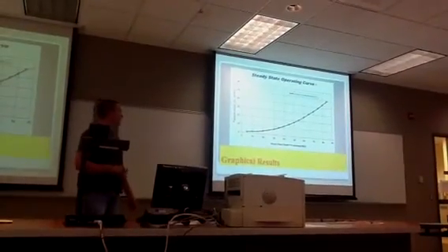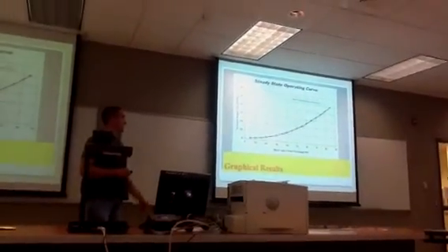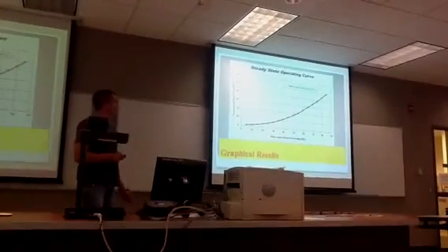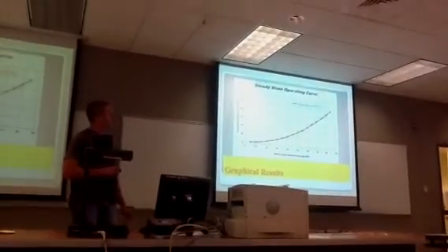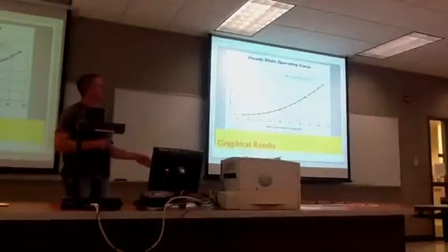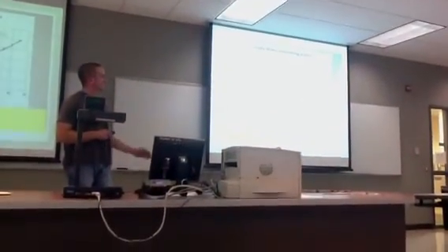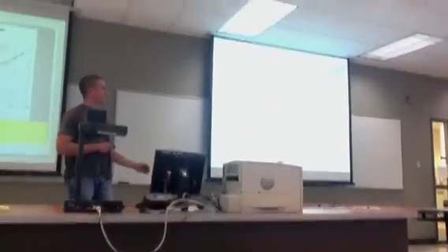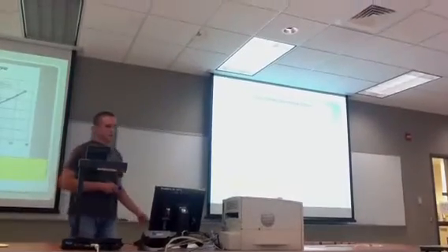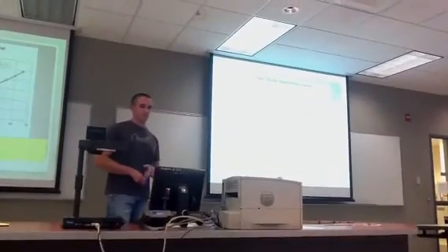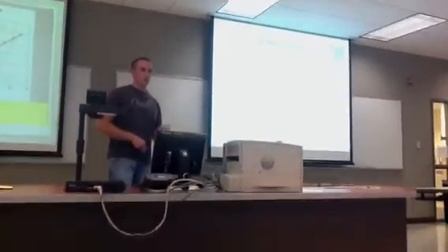This is the output, which was our steady state operating curve, and as you can see, from around 65 to 85%, it goes close to linear. So we set this up as our operating range. That's where the motor wanted to be. It was most predictable in this range. There wasn't as much uncertainty.